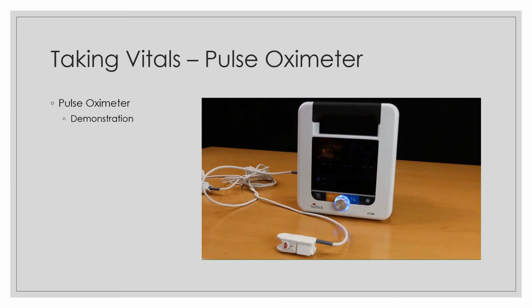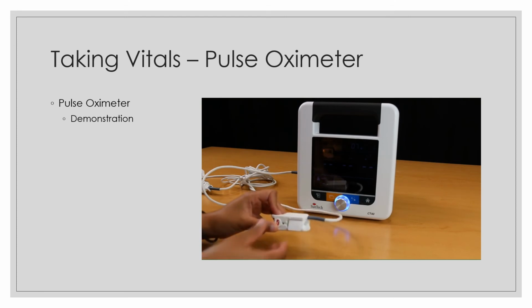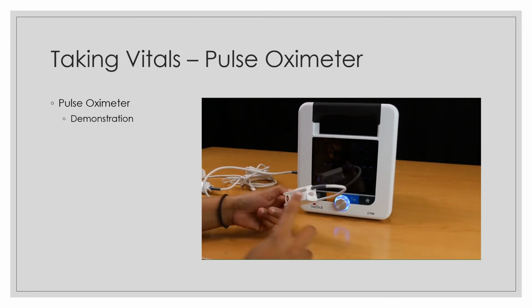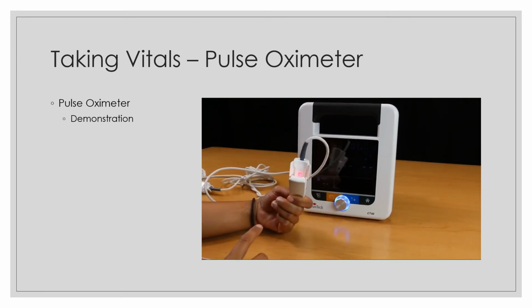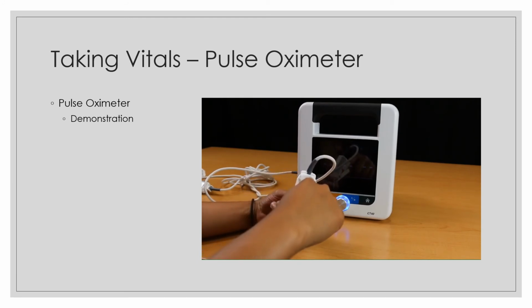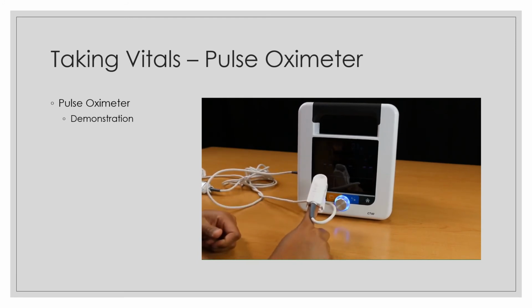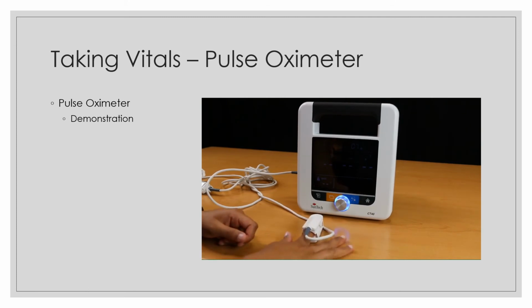After your SpO2 module has been properly installed, begin by inserting either the index, middle or ring finger of your patient into the SpO2 sensor until the end of the finger reaches the finger stop. Do not use the thumb. The fingernail should face the side with the red light. Make sure that long fingernails do not interfere with proper finger position.